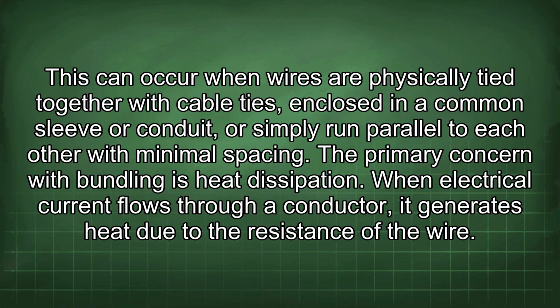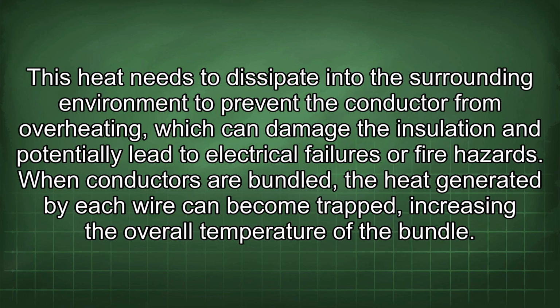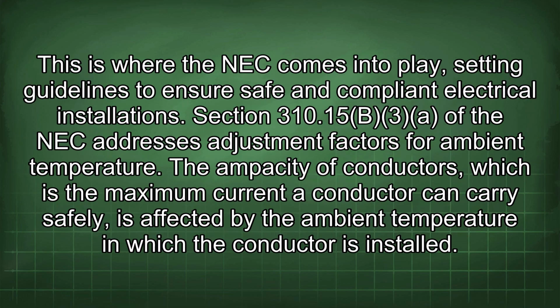The primary concern with bundling is heat dissipation. When electrical current flows through a conductor, it generates heat due to the resistance of the wire. This heat needs to dissipate into the surrounding environment to prevent the conductor from overheating, which can damage the insulation and potentially lead to electrical failures or fire hazards. When conductors are bundled, the heat generated by each wire can become trapped, increasing the overall temperature of the bundle. This is where the NEC comes into play, setting guidelines to ensure safe and compliant electrical installations.